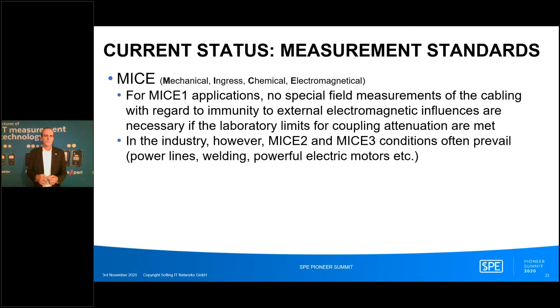Power lines, welding machines, powerful electric motors, all kinds of things that send out a lot of electromagnetic interferences. So cabling has to be very robust against those interferences, and we have to find test methods to test that. So one thing is, for unshielded cables, you can use the TCL measurement. For shielded cables, there are still discussions, and it's not clear how that will go. And in the laboratory, you can use coupling attenuation measurements.